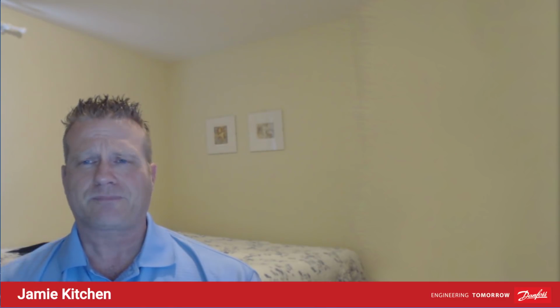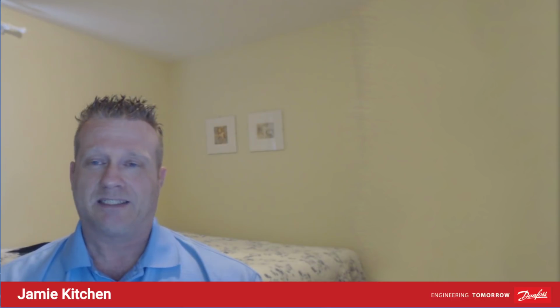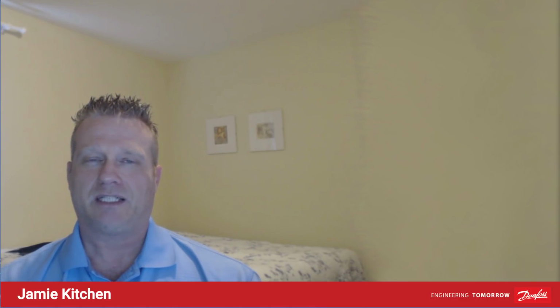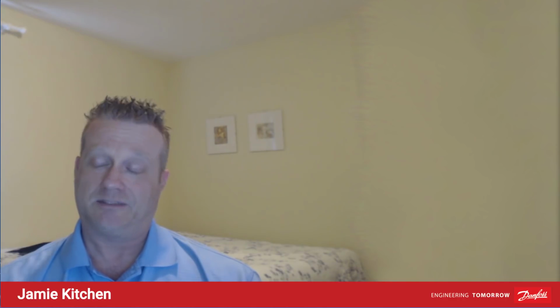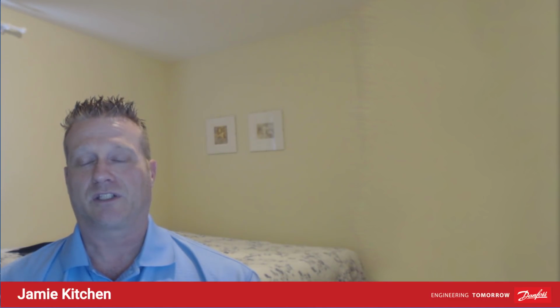Now, my background: I've been with Danfoss for about 20 years, and I'm an engineer, an engineering technologist, as we call it here in Canada. One of my first jobs was working what's called the warranty pile. Nobody liked working the warranty pile, but the good thing about it was you got a chance to see why everything fails in the field. I saw all kinds of burnouts and floodbacks. And to be honest with you, it's pretty true: one third no fault found, one third baked, and one third drowned. There's a lot of truth to that, as far as what we got back, anyway.